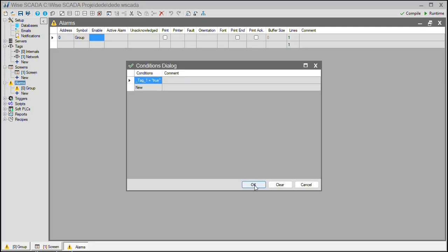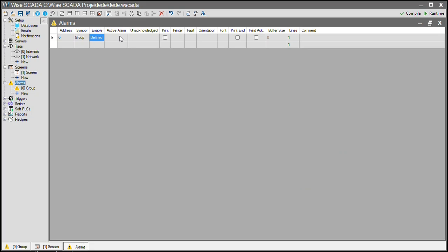Where do we use this feature? For example, we have alarms related to the generator, but these alarms need to be shown when the generator is running. If the engine is not running, these alarms should not be checked. In such a case, we can use the enable bit.